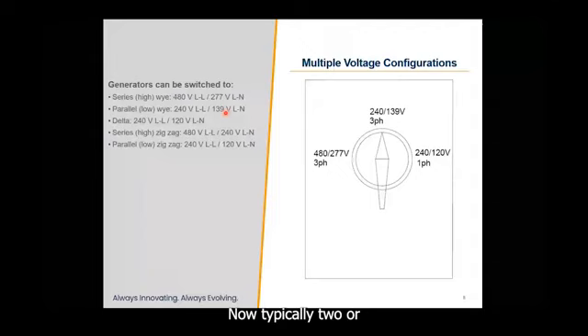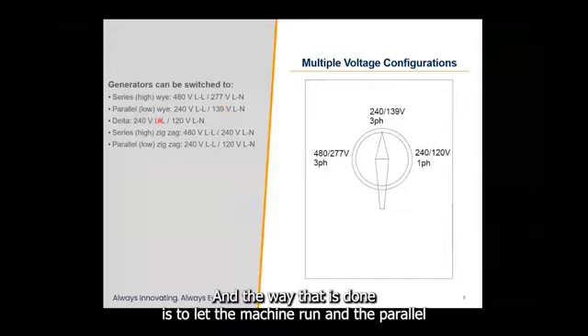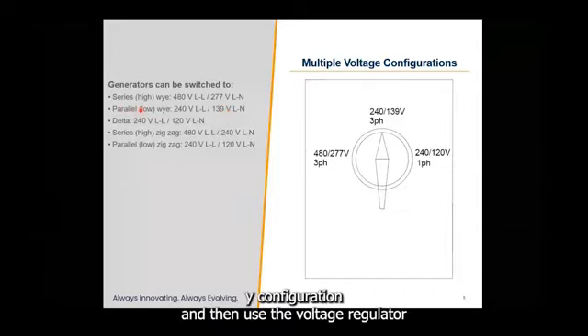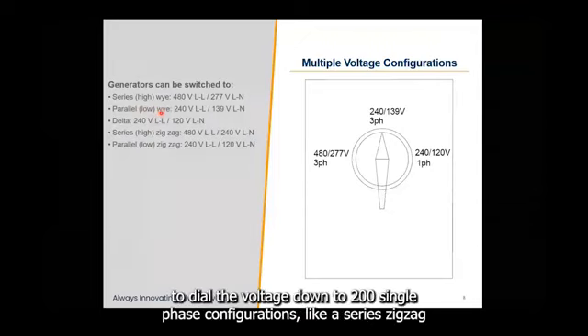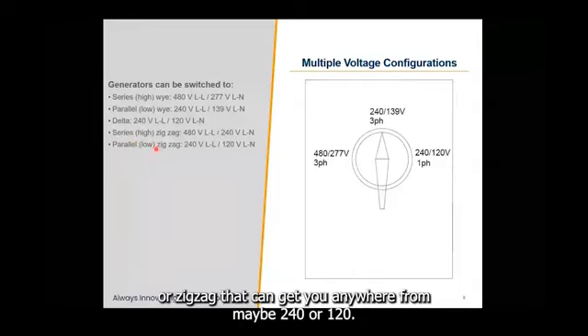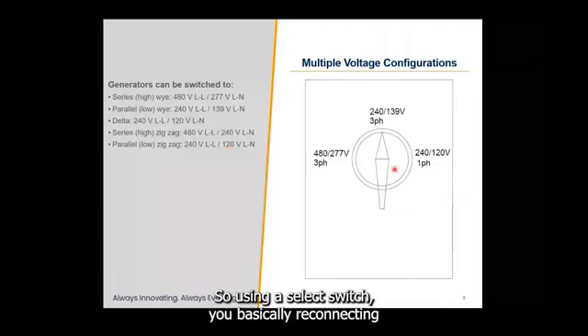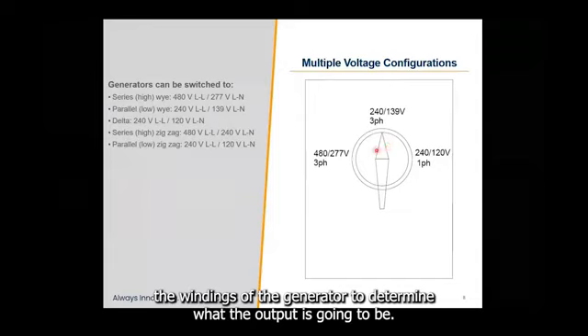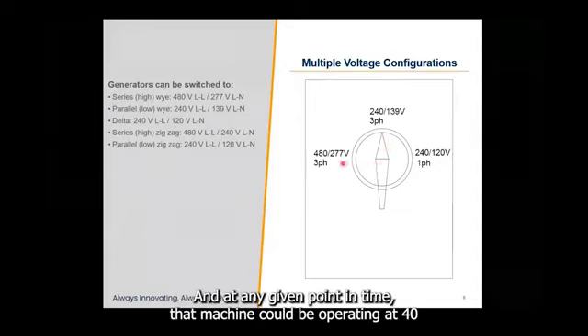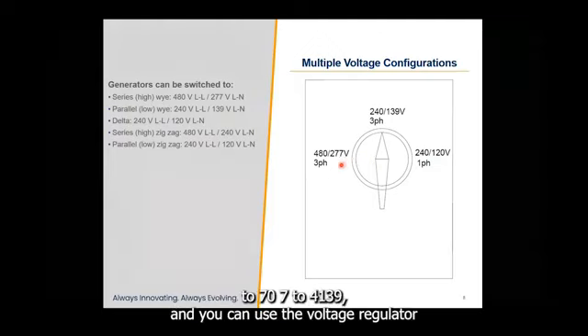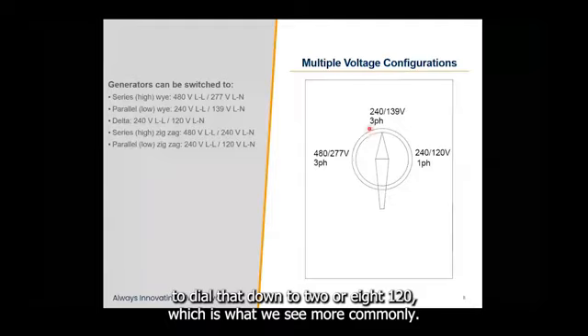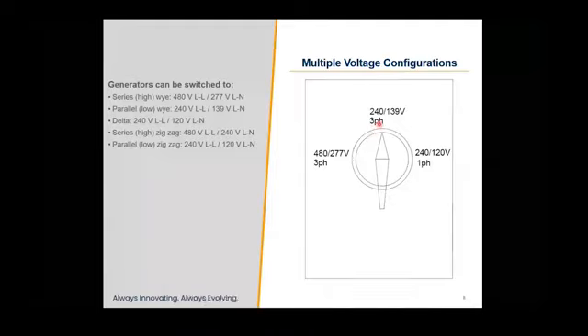Now, typically 208 line to line, 120 line to neutral is used. And the way that is done is to let the machine run in the parallel Y configuration and then use the voltage regulator to dial the voltage down to 208. I'll take single phase configurations like a series zigzag or parallel zigzag that can get you anywhere from maybe 240 or 120. So using a select switch, you're basically reconnecting the windings of the generator to determine what the output is going to be. At any given point in time, that machine could be operating at 480, 277, 240, 139, and you can use the voltage regulator to dial that down to 208, 120, which is what we see more commonly, or it could be a single phase configuration, either 240 or 120 volts.